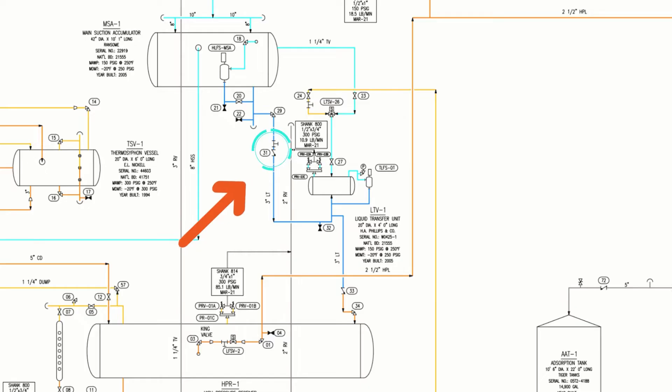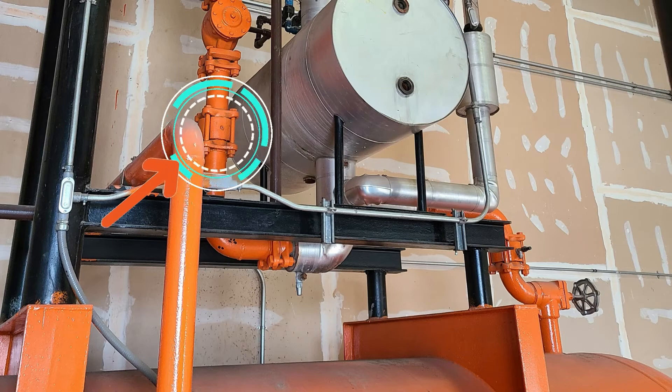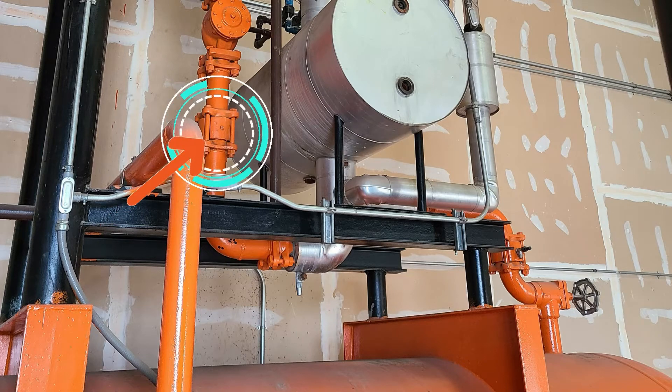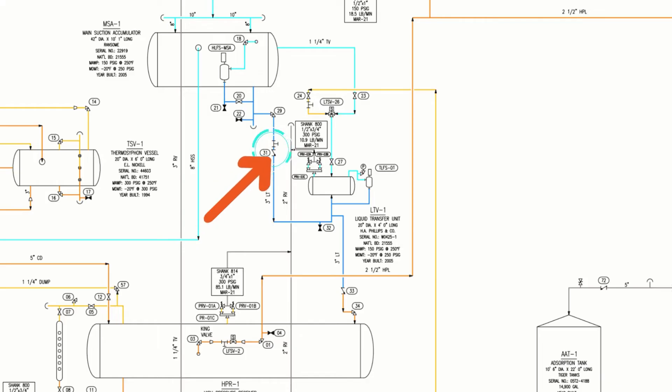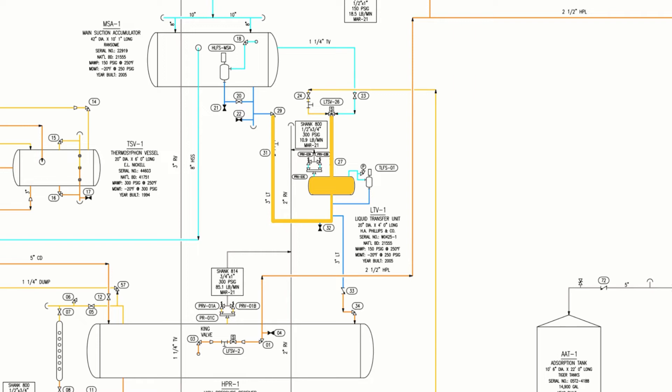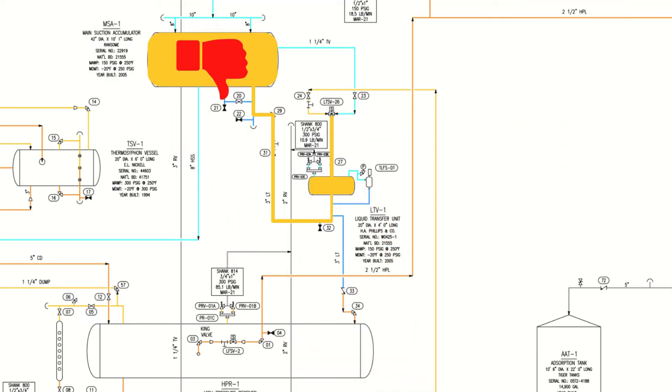The check valve between the suction accumulator and the liquid transfer vessel fails open, allowing high-pressure vapor to enter the suction accumulator when a transfer is initiated. Without a P&ID, it is hard to visualize what is occurring in this scenario. But if this were to occur, high-pressure liquid would enter the suction accumulator when the liquid transfer is initiated. This would result in tripping the high-level float switch or possibly slugging compressors with liquid.